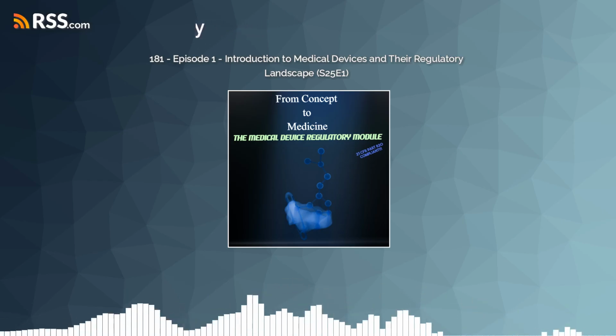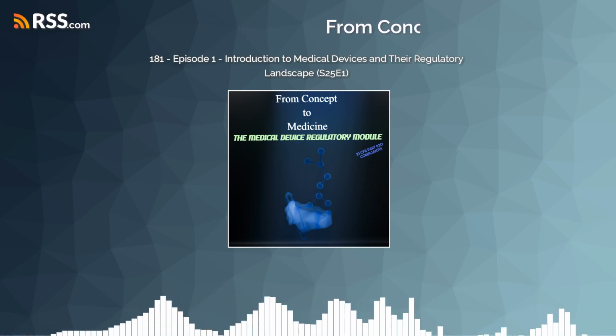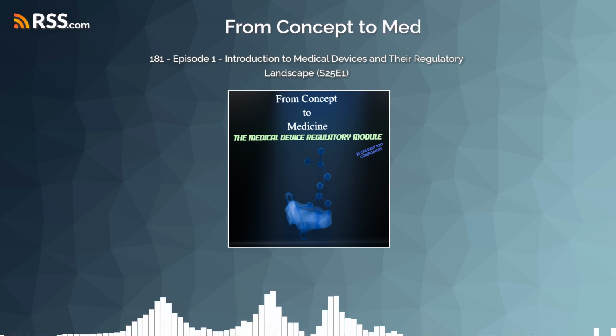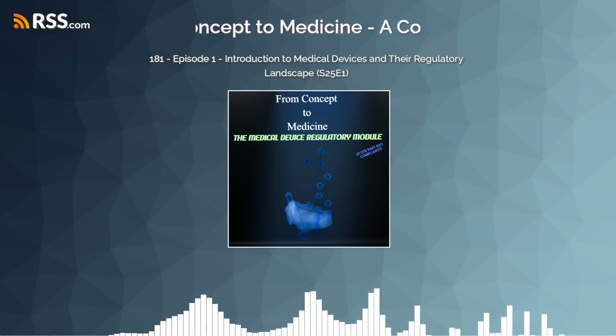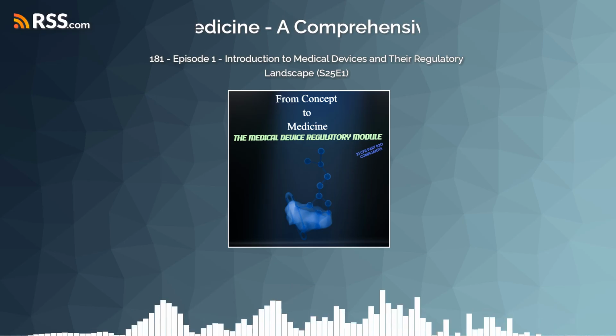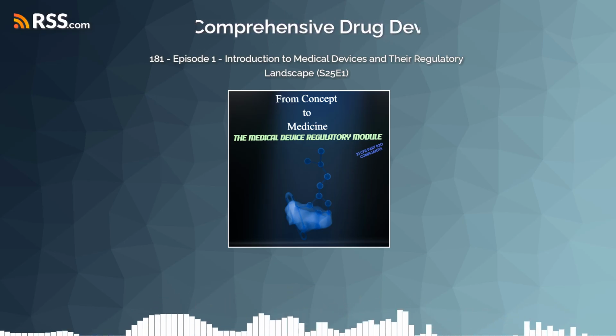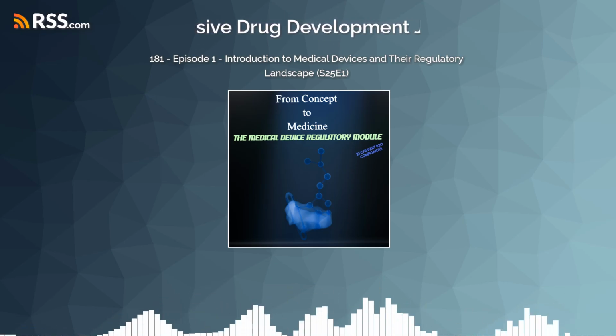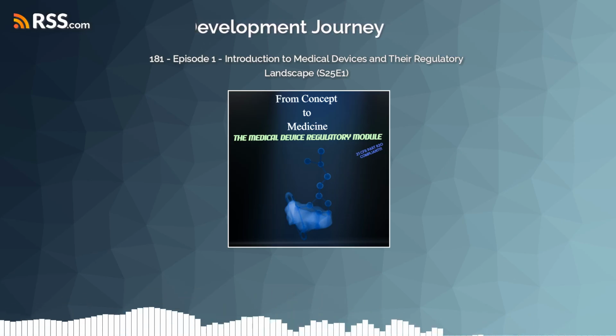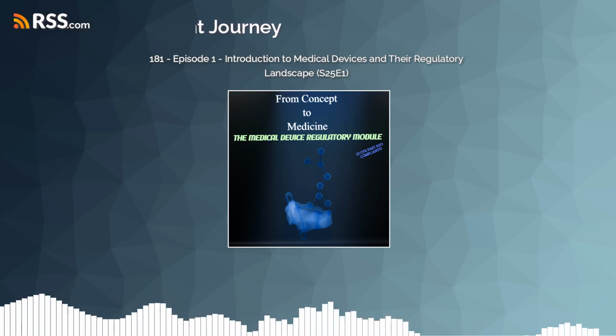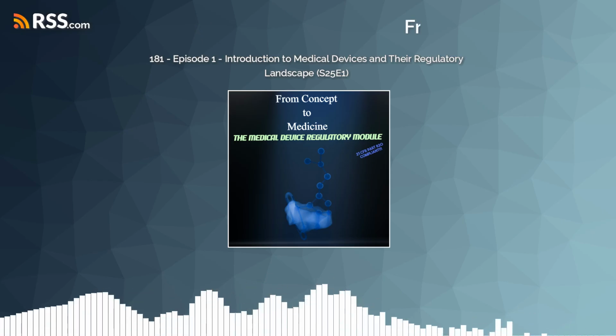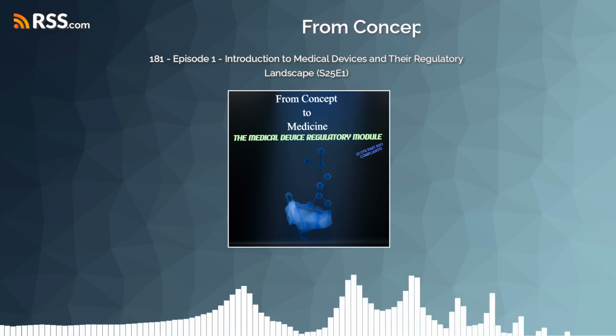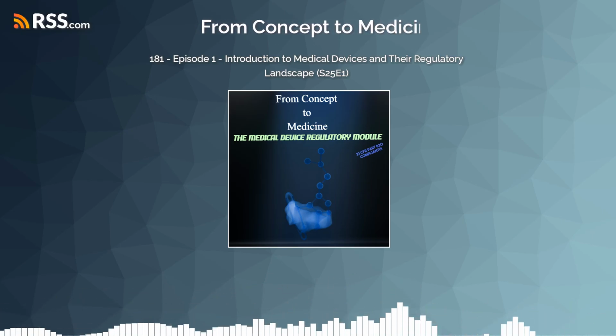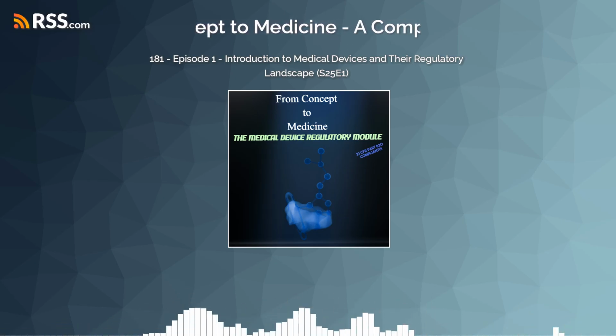Almost always for PMA. The FDA needs robust evidence that the benefits outweigh the risks for these high-risk devices. They may even refer the PMA to an advisory panel of external experts for review and recommendation. It's a very thorough process. Okay. What are some classic examples of Class 3 devices, the kind that really illustrate this high-risk profile? Well, pacemakers and implantable heart valves are definitive Class 3 devices, life-sustaining implants.